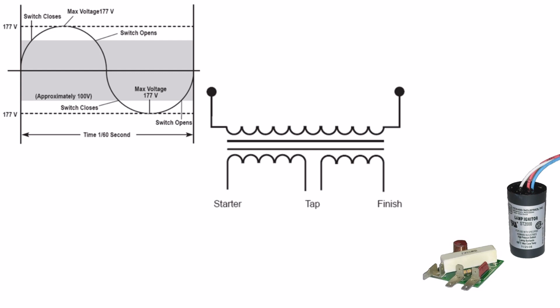Let's explain how the starter works using a car engine analogy. In a car, you have spark plugs that ignite fuel. You have breaker points that open and close to generate a spark. You have a coil to boost the voltage, and a condenser or capacitor that helps with the timing. A high-pressure sodium starter works in almost the same way. The arc tube electrodes act like spark plugs. The electronic switch is like the breaker points. The capacitor helps boost the voltage, and the ballast acts like an ignition coil, ramping up voltage like a mini transformer.